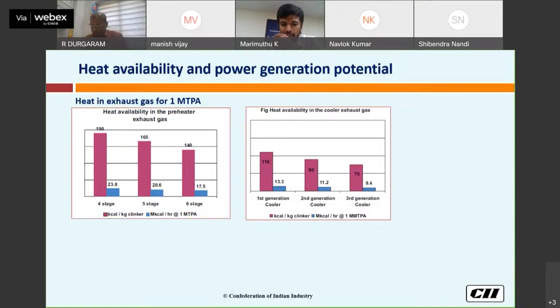The preheater gas usage is mainly based on the raw mill moisture. If you have more moisture, we have to utilize it for drying, or otherwise you can use it for power generation. And on the clinker cooler side, if we consider a third generation cooler for 1 million ton per annum clinker generation, we will have a heat content of around 9.4 kilocalorie.